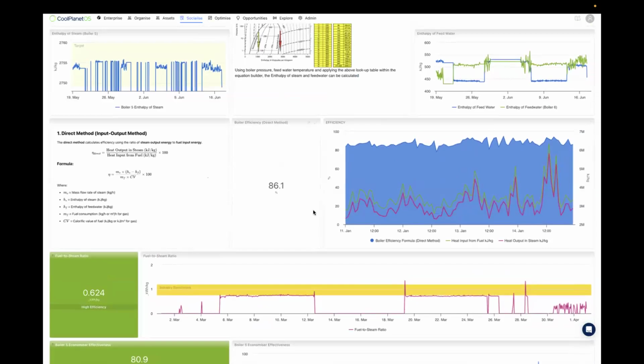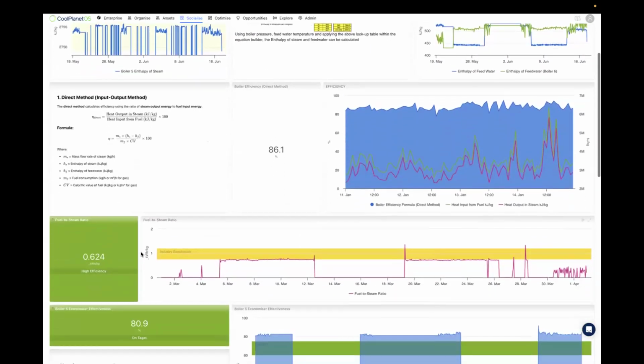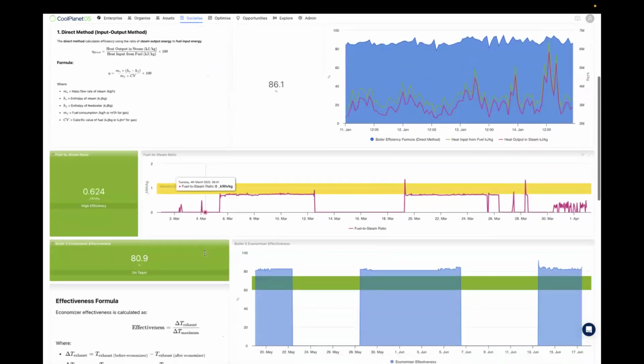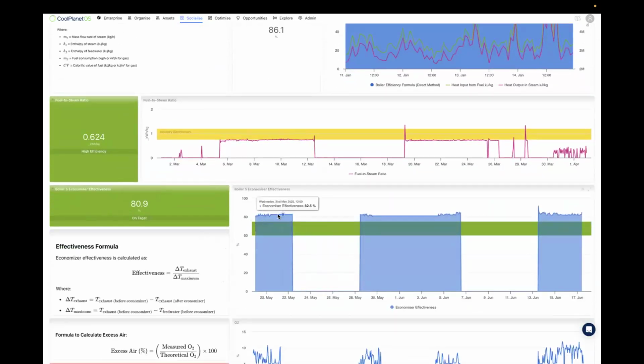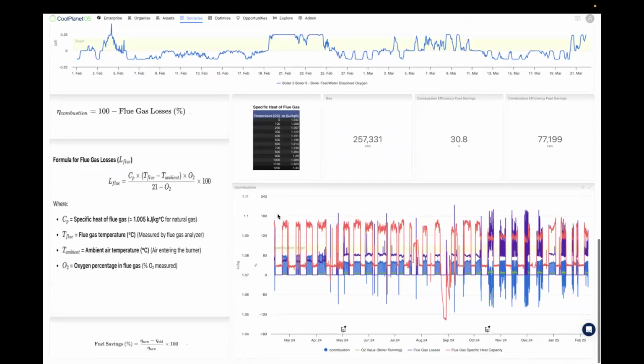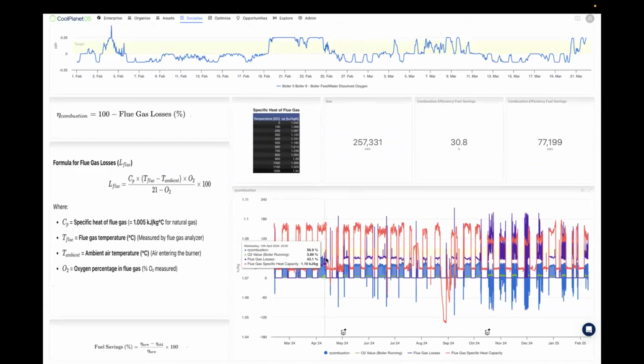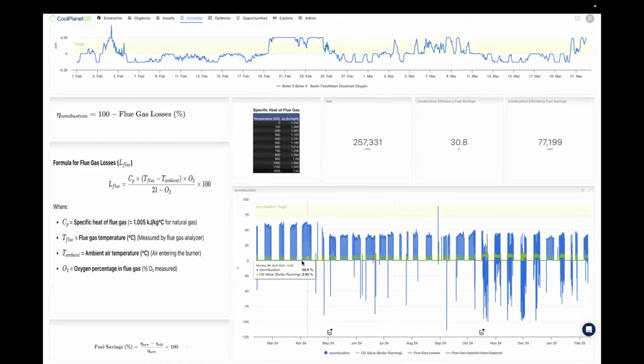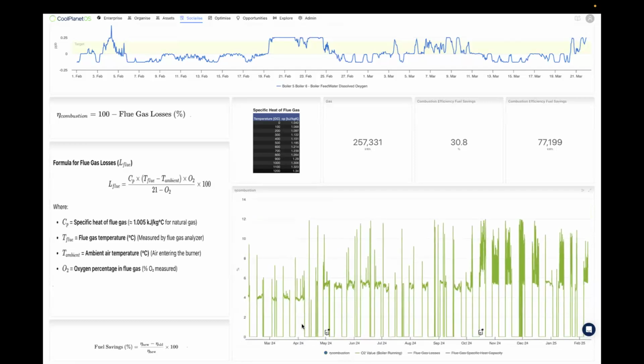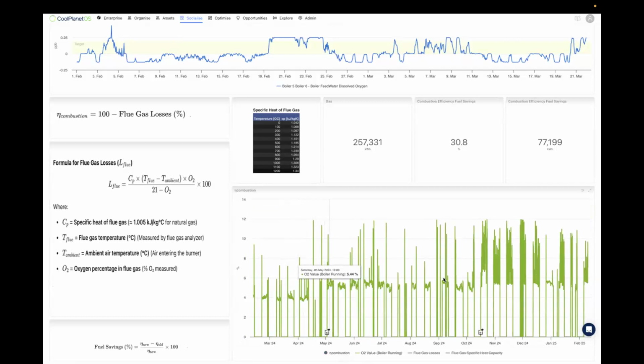We had optimized it previously, so you can see efficiencies are up to 86. Fuel to steam ratio is exactly where you want it. A boiler economizer is exactly where you want it versus industry target or standards. But then when we start looking at the combustion efficiency and the O2 levels, we started to see cracks in the system. So this is the combustion efficiency, this blue trend. You can see a really evident step change around here, and then a further step change around here. And that correlates with O2 levels. So O2 increased at the same period and increased again in this second period.